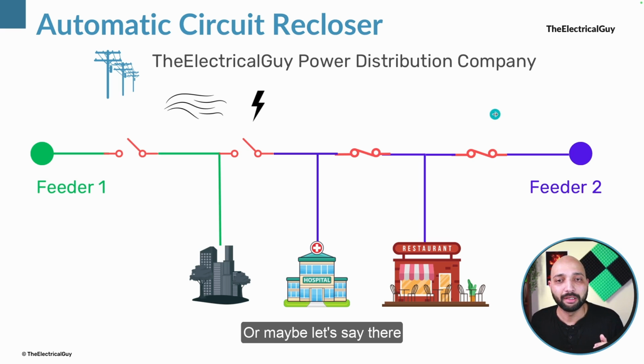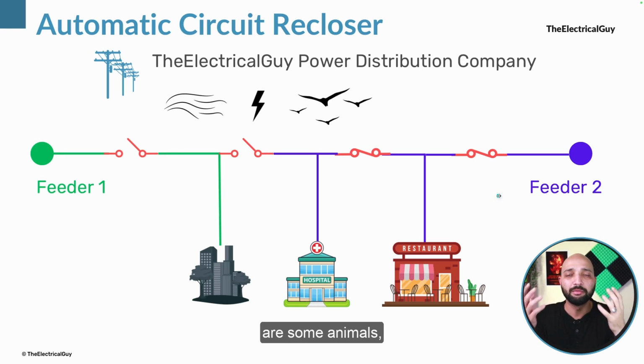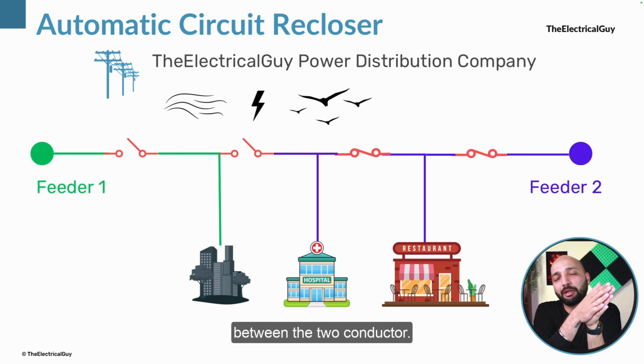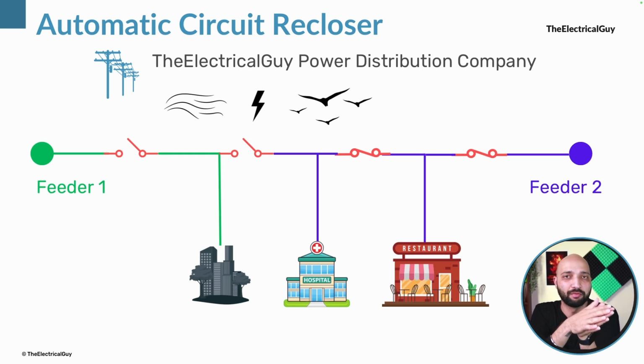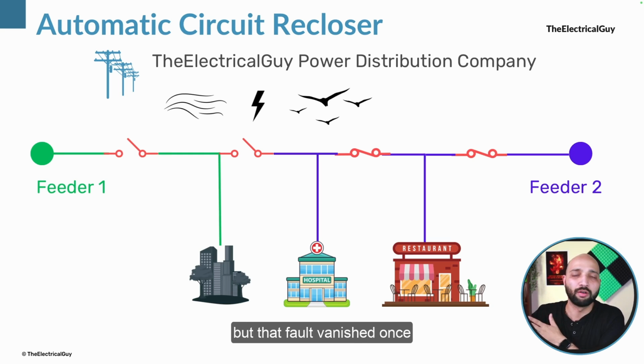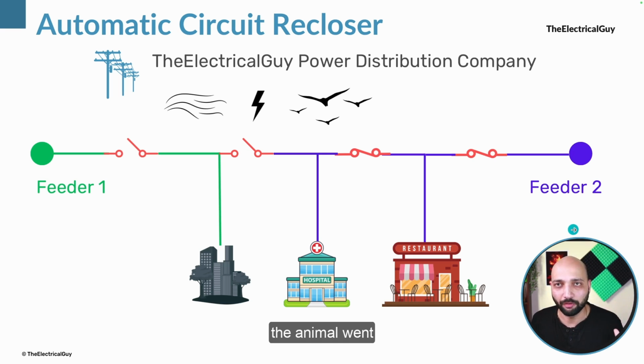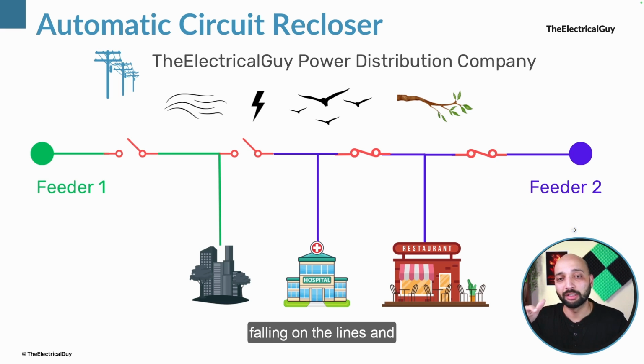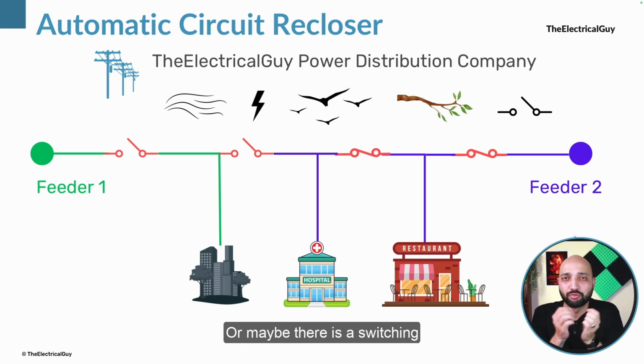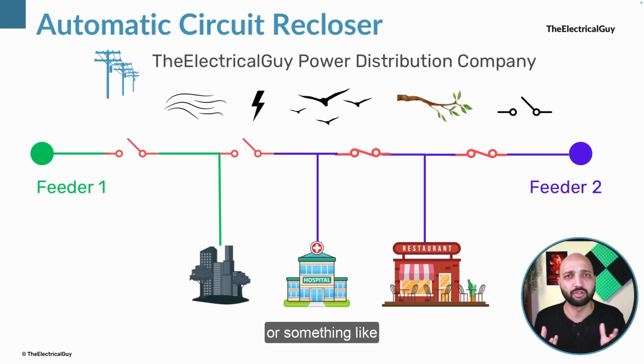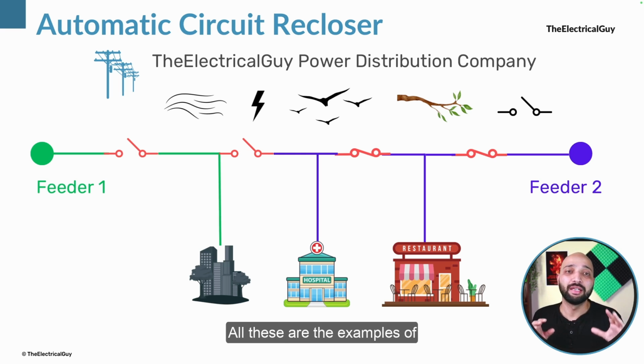Or maybe there are some animals or birds that bridge the gap between the two conductors and as a result there is a fault. The circuit breaker opens but that fault vanishes once the animal goes off. Or maybe a tree branch falls on the lines and then there is a fault. Or maybe there is a switching surge for a few milliseconds or something like that. All these are examples of the reasons for temporary faults.